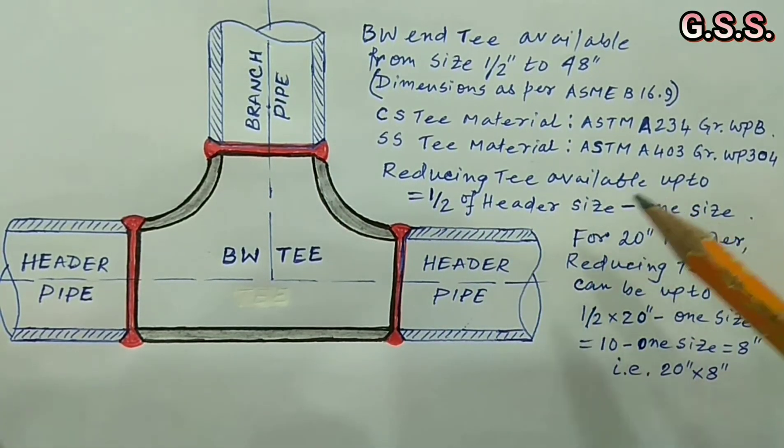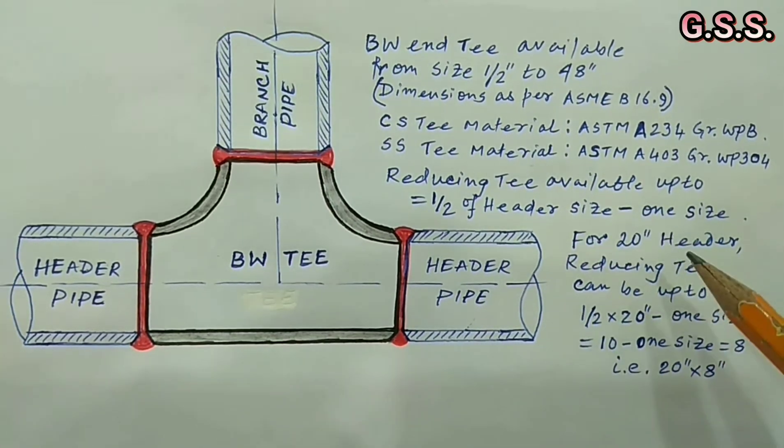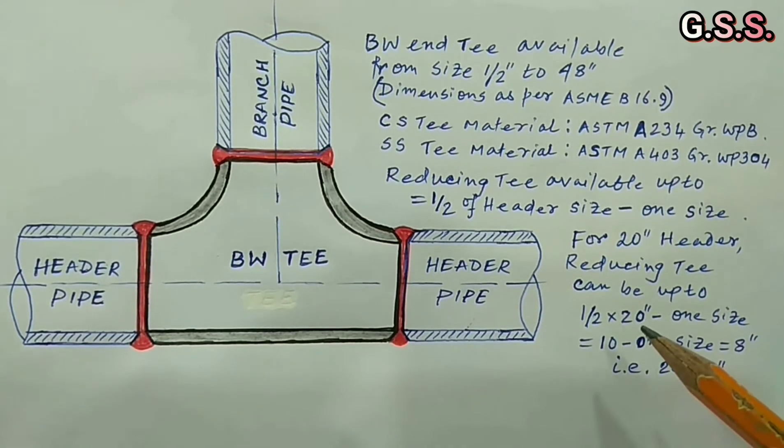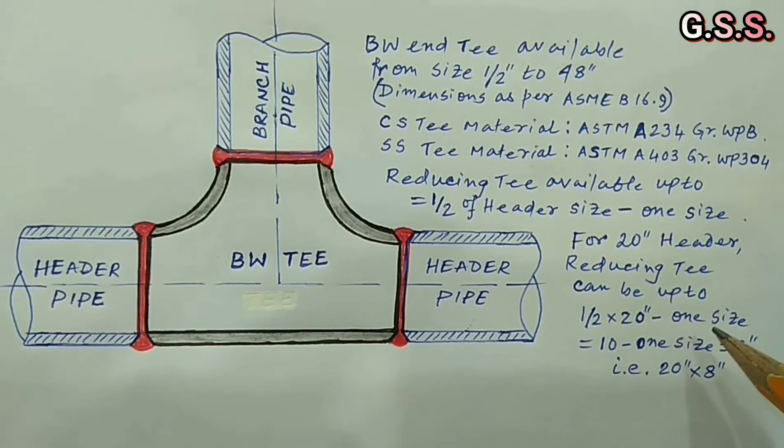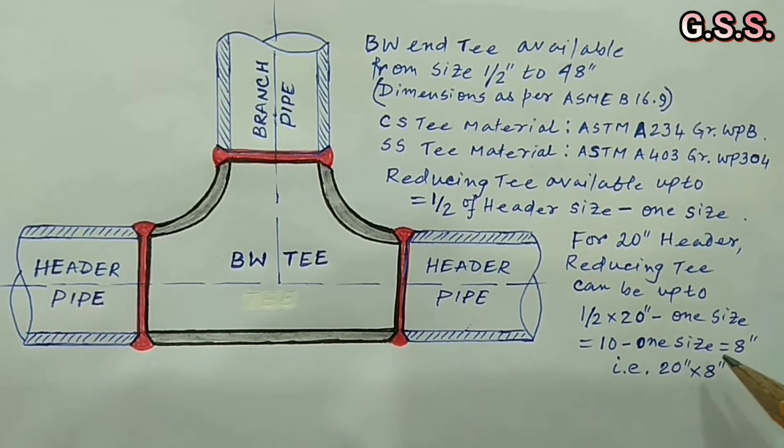Reducing Ts are available up to size half of header size less one size. That means for 20 inch header size, reducing T is possible up to 20 inch by 8 inch size. That means half of 20 inch less one size, that means 10 inch minus one size, that means 8 inch.